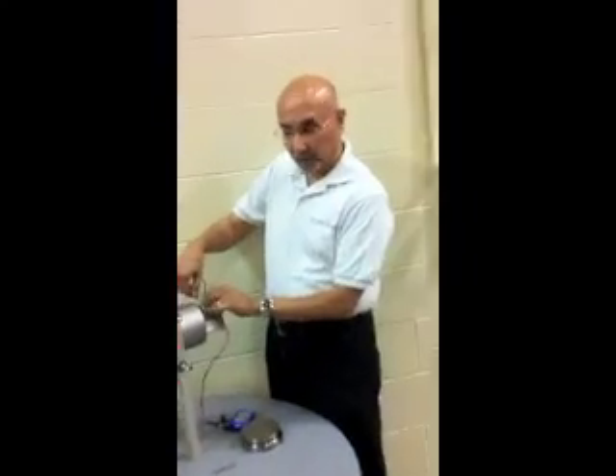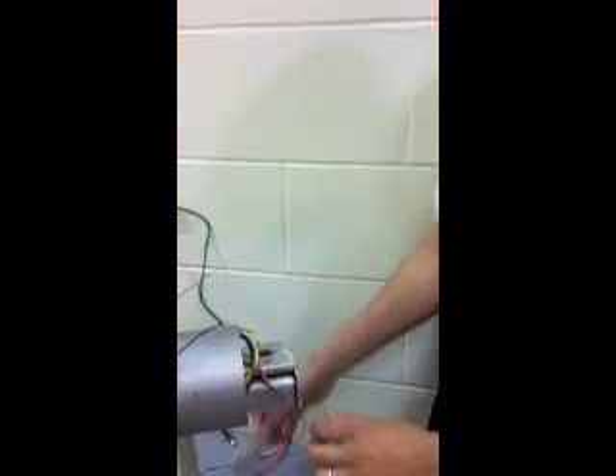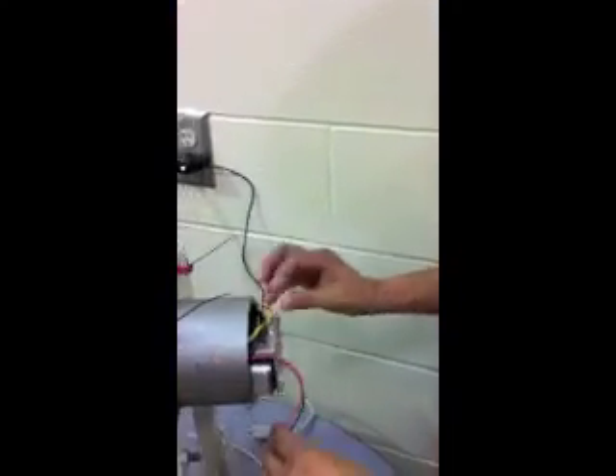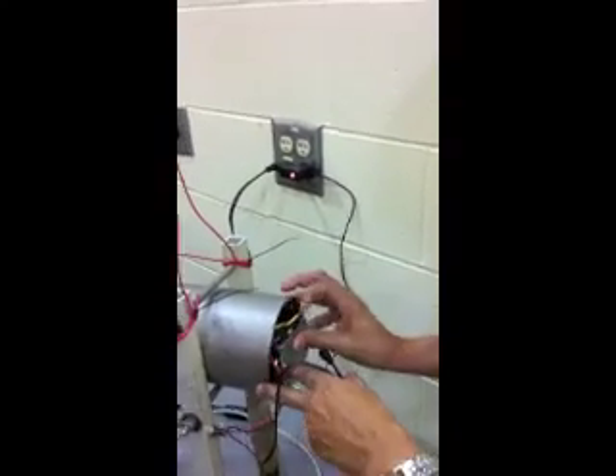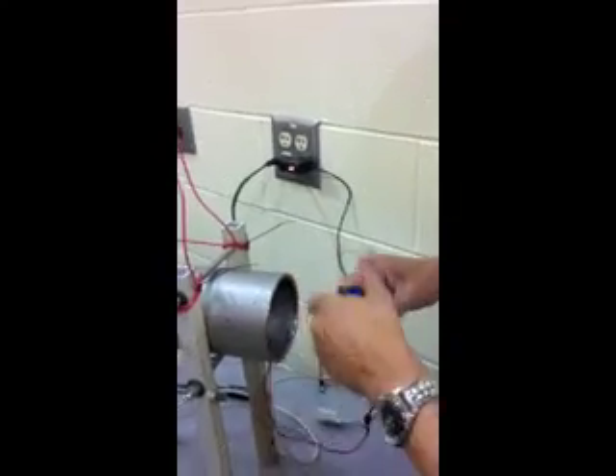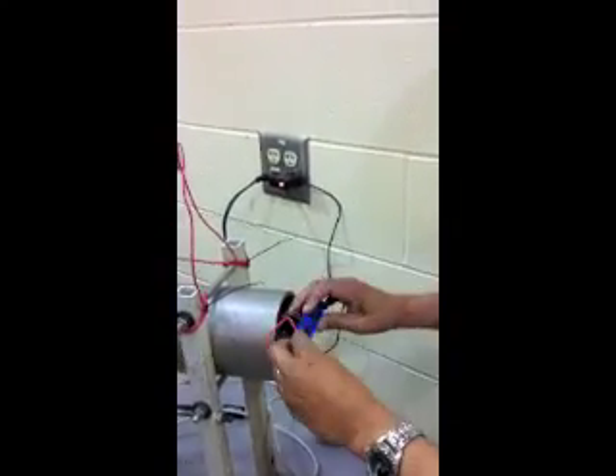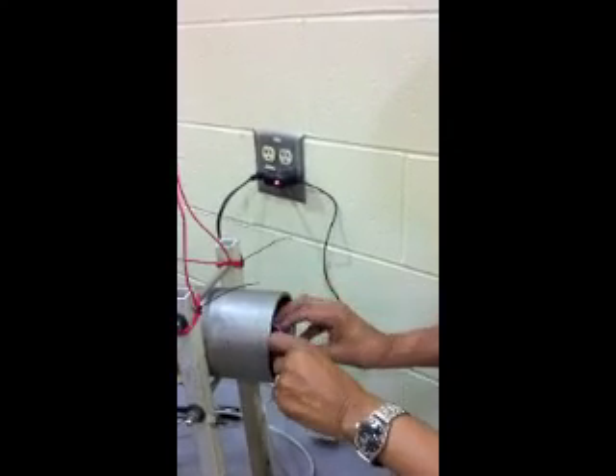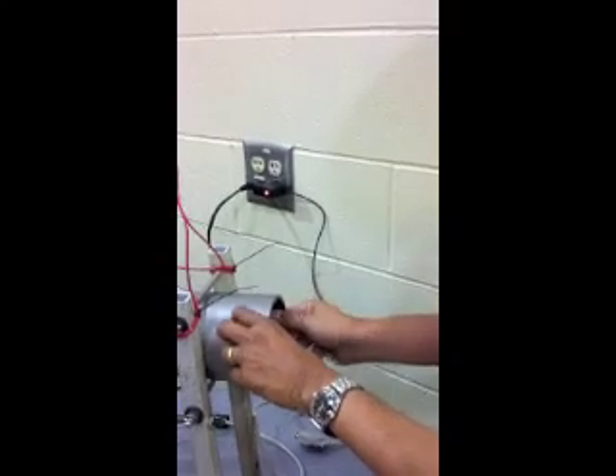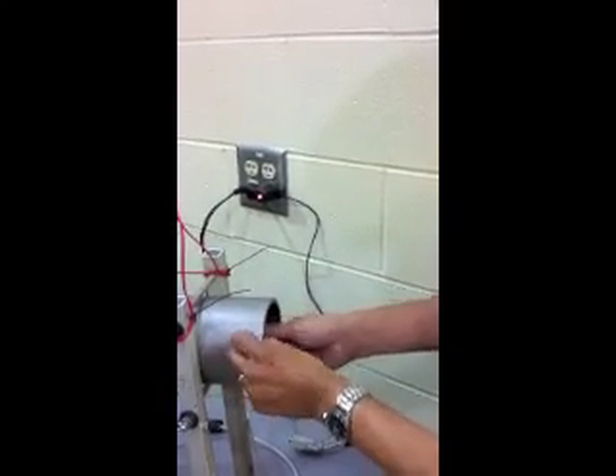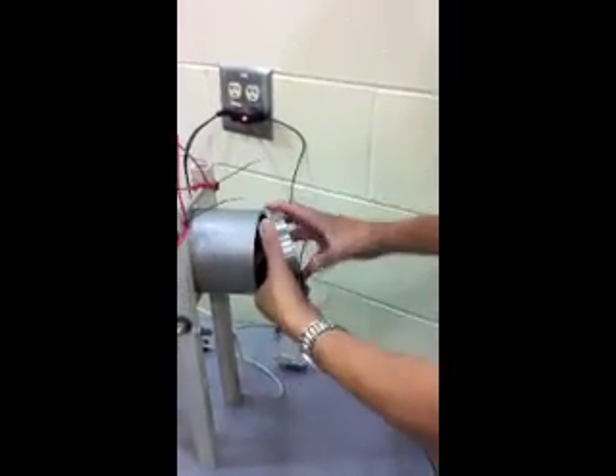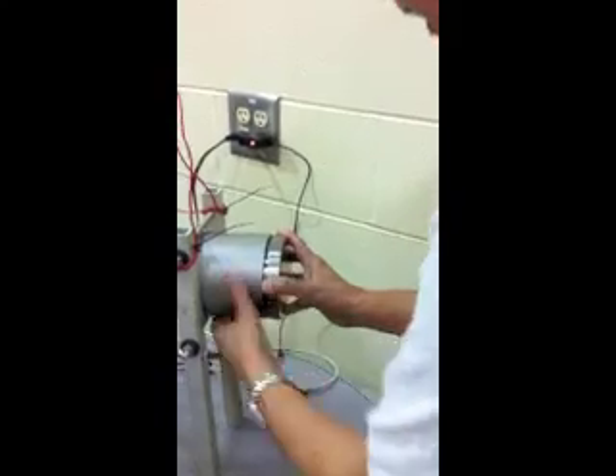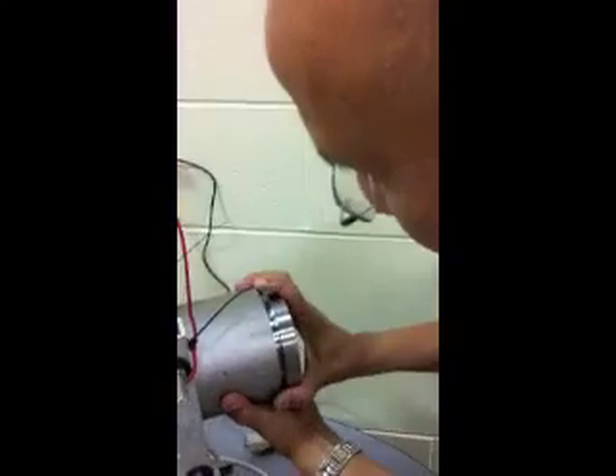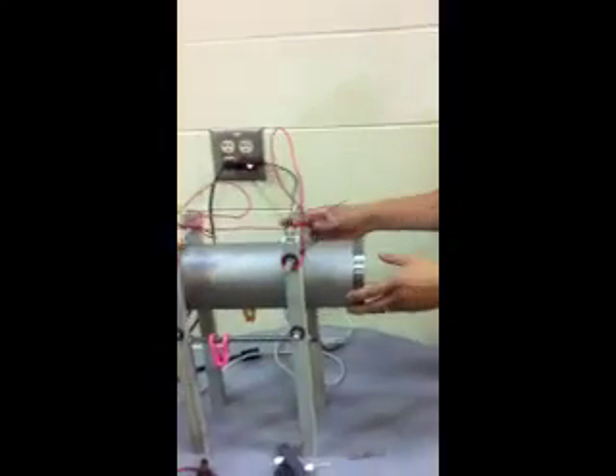Okay. Now we are ready to close up the system, so we disconnect the serial I/O port. We push back the data logger into the enclosure, and also the battery pack. Taking a little care to be gentle about this, because we want to be sure that we don't disrupt any of the connections. So once this is in place, we can replace the end piece, and this can be pressed in with a little bit of pressure and by twisting slightly. And it would be a good idea to push on both ends of this, and one can essentially close this up without too much effort.